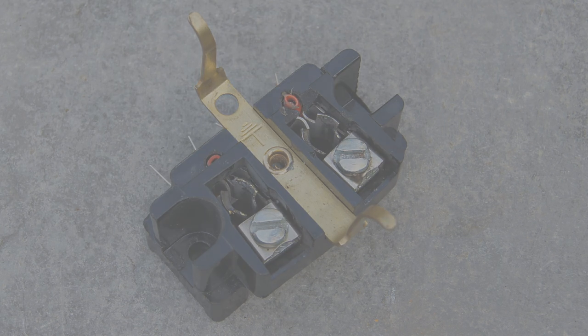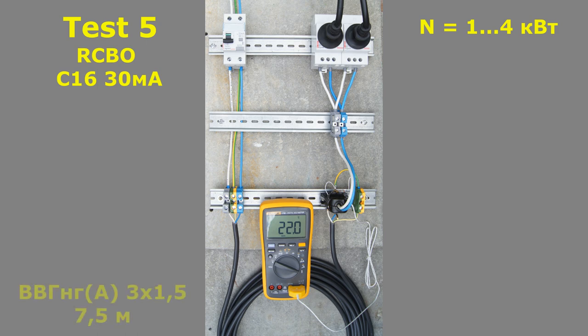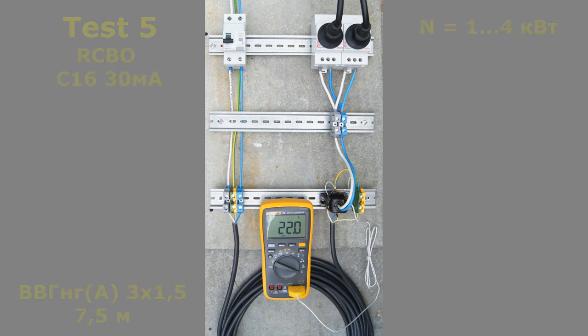Let's continue numbering the experiments of the first part and simplify the assembly. There will be a C16 RCBO at the input. We will limit the maximum load to 4 kilowatts for it. We connect it through a plug and auxiliary sockets. To simulate the remote location of the outlet, power supply will be carried out again through a 7.5 meter long cable. We intentionally form bad contacts between the pins and sockets of the connecting device, as well as between the cable conductors and the outlet clips. We do not tighten them.